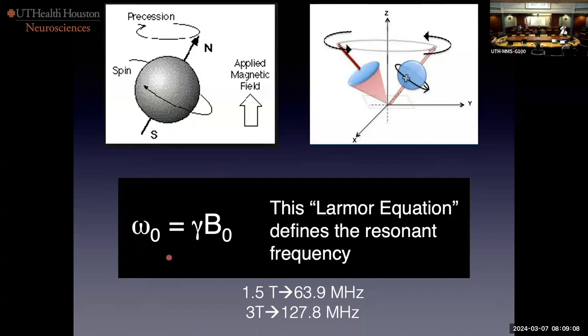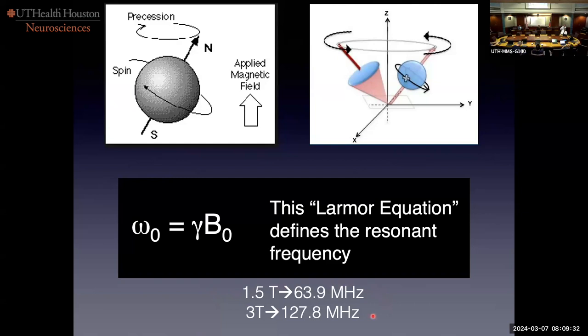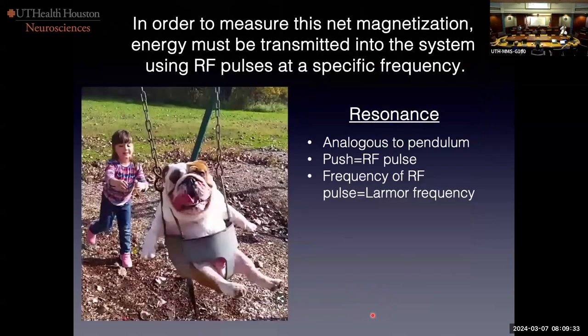The frequency of precession is equal to the gyromagnetic ratio — which is different for any single nucleus — times the magnetic field strength. So if you're in a 1.5 tesla, your protons are precessing at 63.9 megahertz. You get into 3 tesla and it's twice the frequency. So now I've covered why it's nuclear and why it's magnetic — let's talk about resonance.